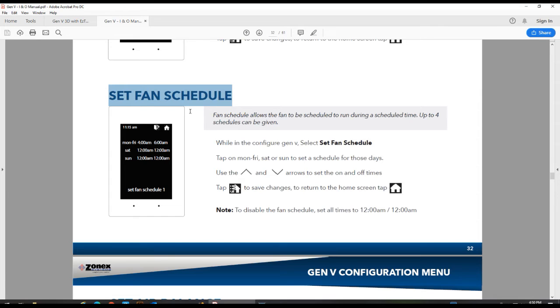Set fan schedule. This is a newer feature to the Gen V control system. This came about due to COVID and wanting to run the fan on its own schedule. So if you're running UV lights or air scrubbers, you can give a schedule to the fan, and you can do up to 4 schedules per day. So go ahead and set the schedule according to what the operation you want.